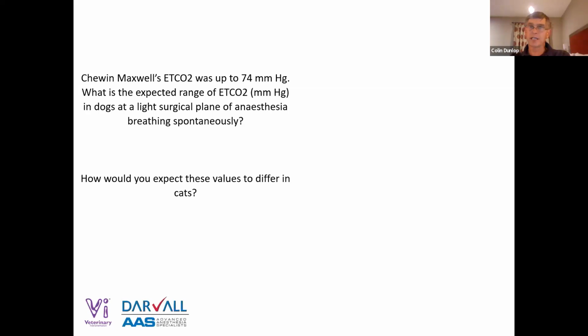And 60 is too high for a dog at a light plane of anaesthesia. It should have a CO2 below 55. If I walk past a surgery room and I look up at the screen of a capnograph and I see over 55, 56, 57, 60, I'm going to walk in and take a look at that patient. 70 is way too high.